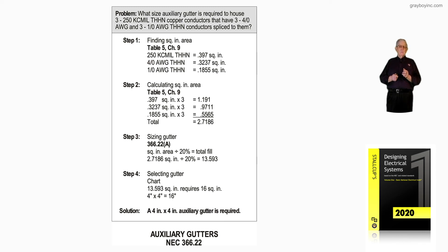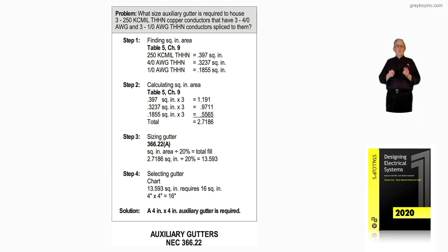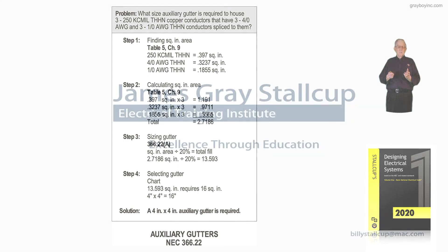We would go to the chart on the back inside cover of the design book, and we would take a 4x4, which would be 16 square inches of area. Yes, it will house 13.593 square inches. So the solution and answer is a four inch by four inch auxiliary gutter is required, and will house the square inch area calculated in step two — just like the quick calc showed.